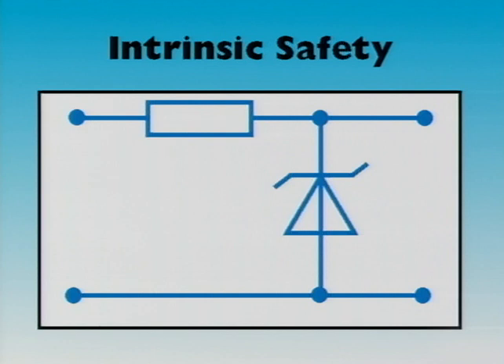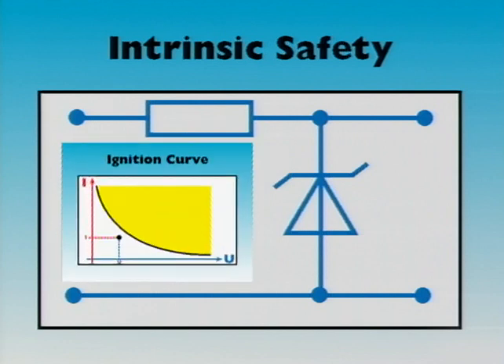Both components limit the electrical energy. Correctly dimensioned, the spark energy lies below the ignition limit curve in the safe area, and the circuit is then intrinsically safe.